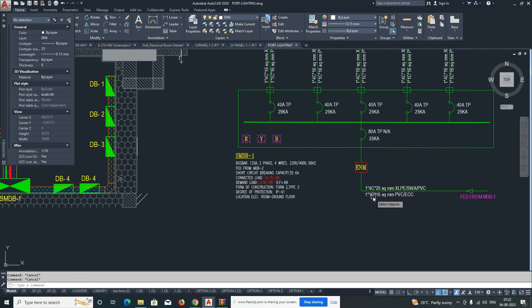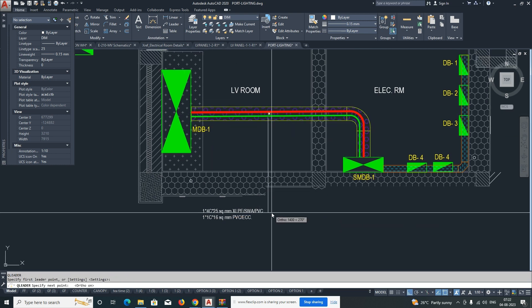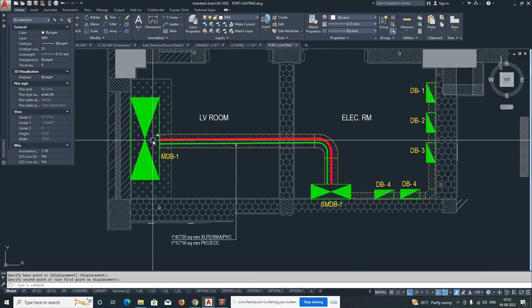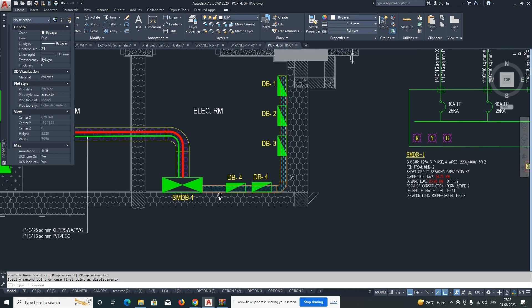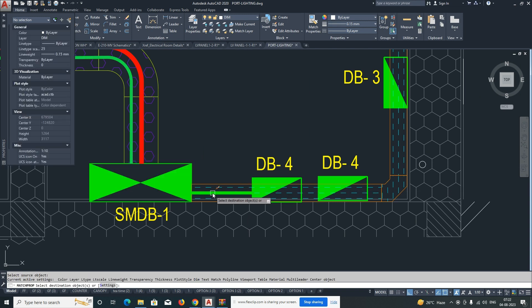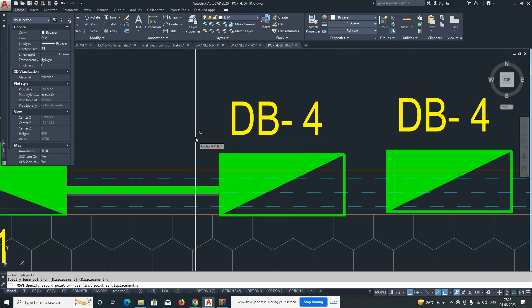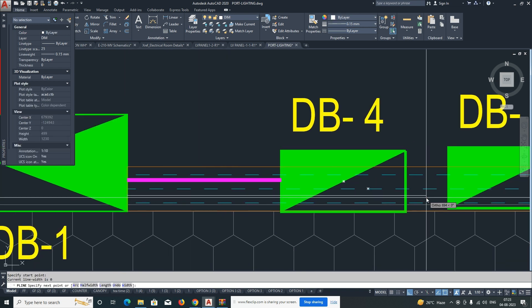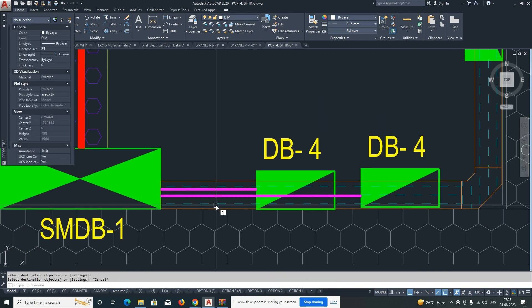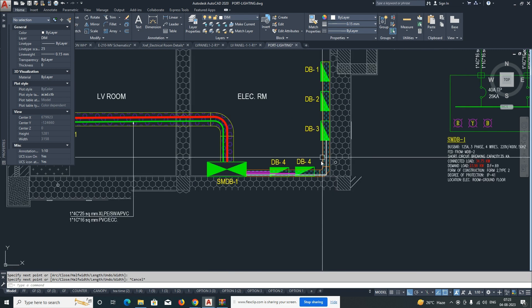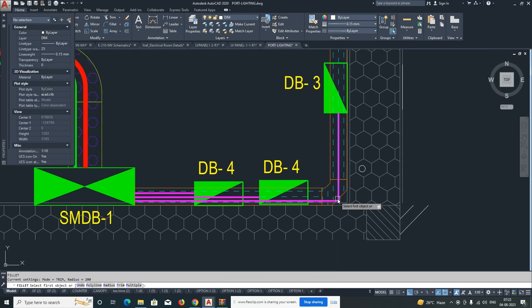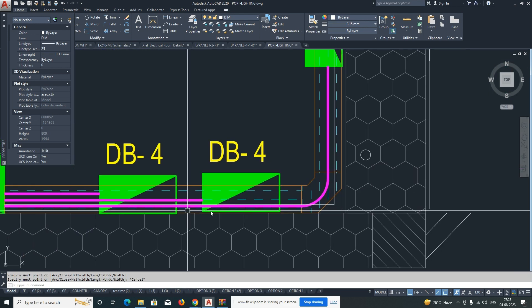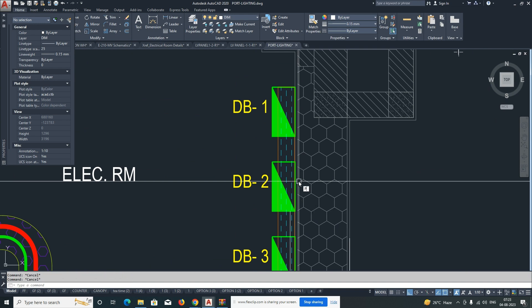We can give some tags using the leader command for all the cables. From here the cable is feeding to the SMDB, and then each cable connects to each DB. For example, DB1 has a 16mm cable connecting to it. I'll change the color to magenta for representation. Other cables come through the cable trunking to each panel. I'll give a width of 100mm and draw the additional cables connecting to each panel through the trunking.